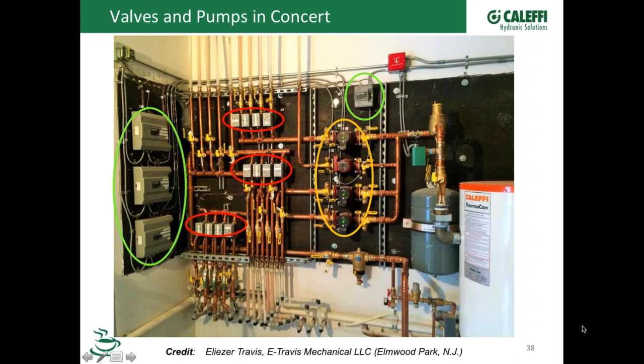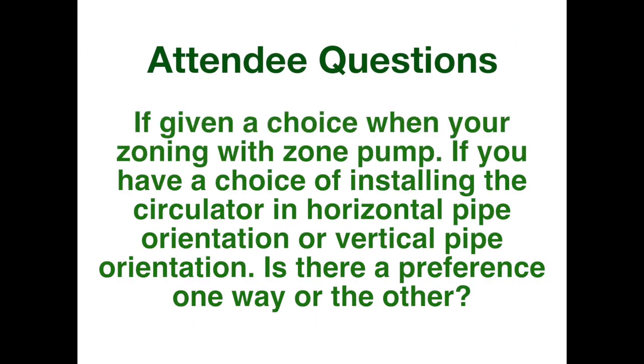Beautiful work. I would be happy to work on this. A job like this puts Max through college. It's got everything Caleffi on there. Fill valve, the dirt separator, air separator, buffer tank over here. One question, maybe a few. If given a choice when you're zoning with zone pumps, if you have a choice of installing the circulator in horizontal pipe orientation or vertical pipe orientation, is there a preference one way or the other?